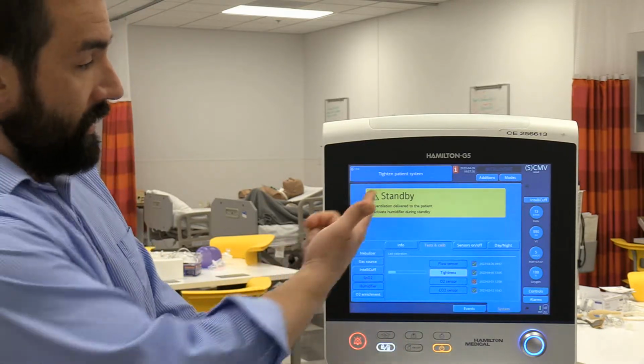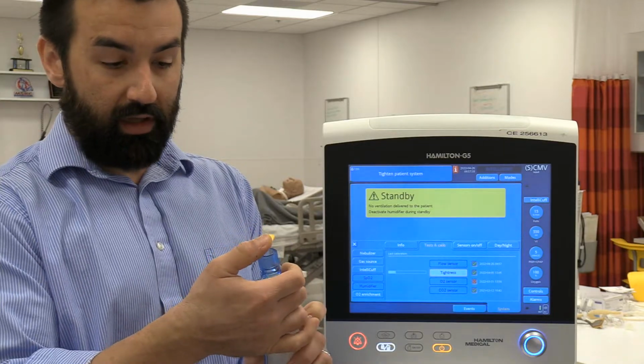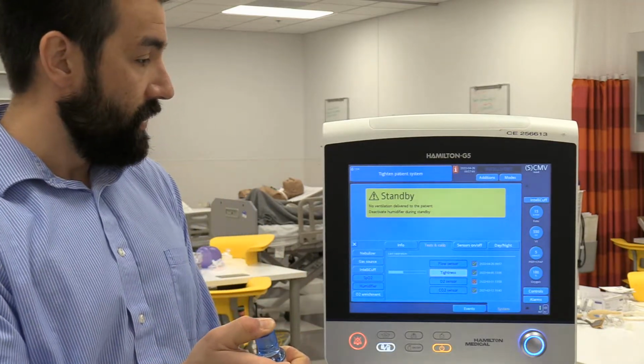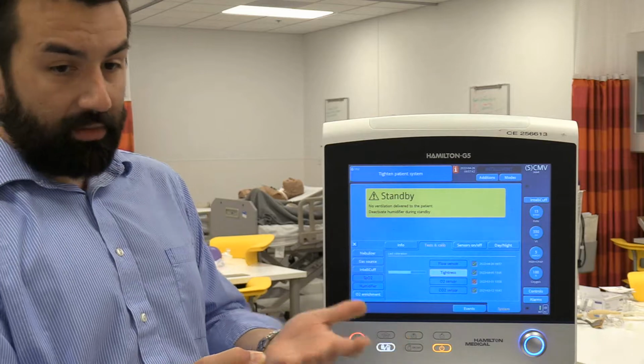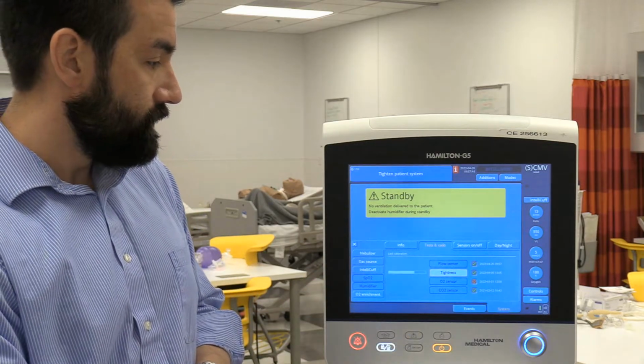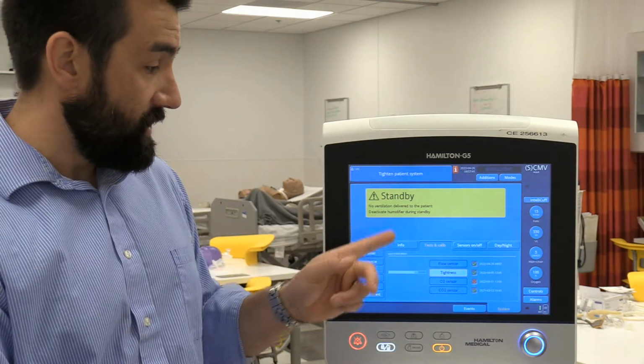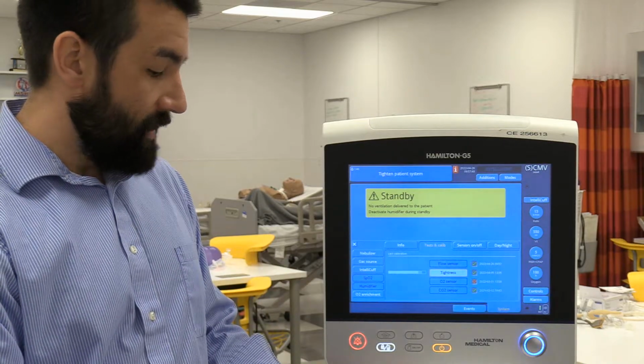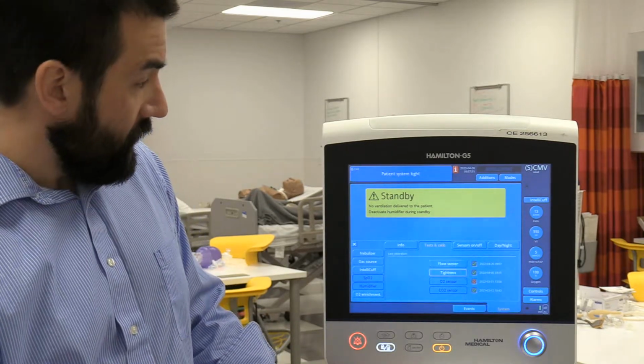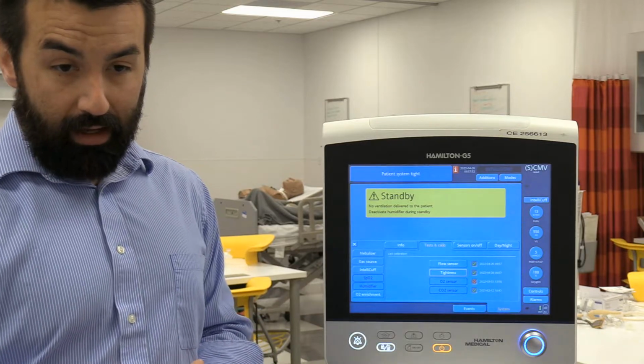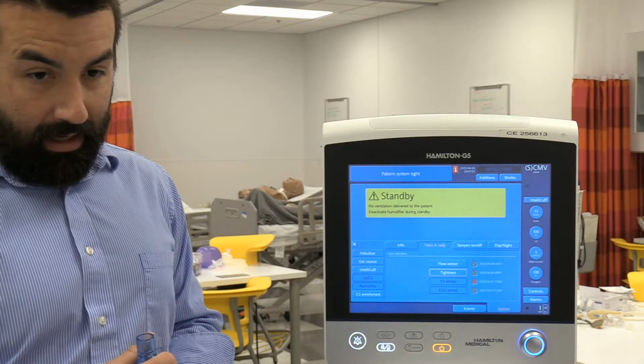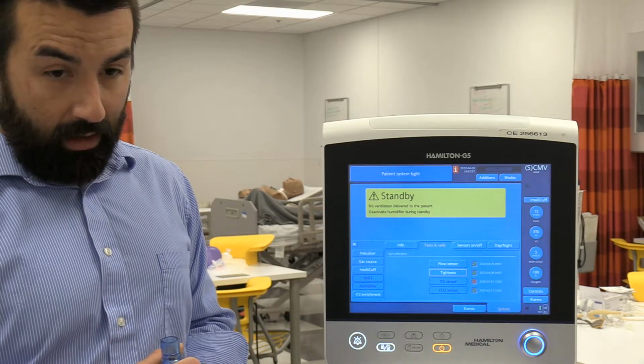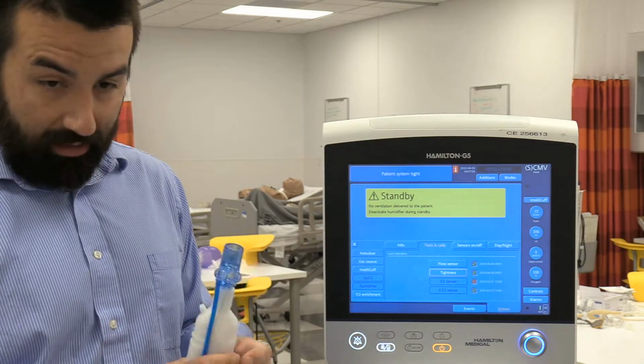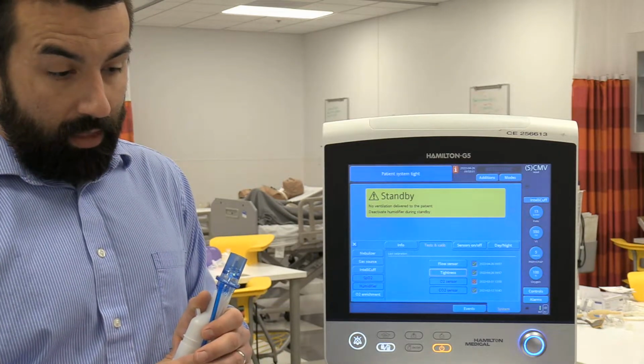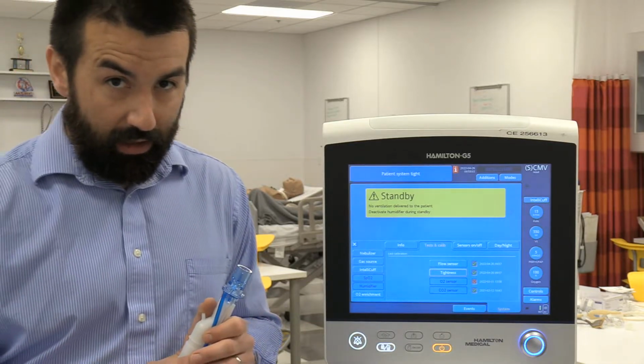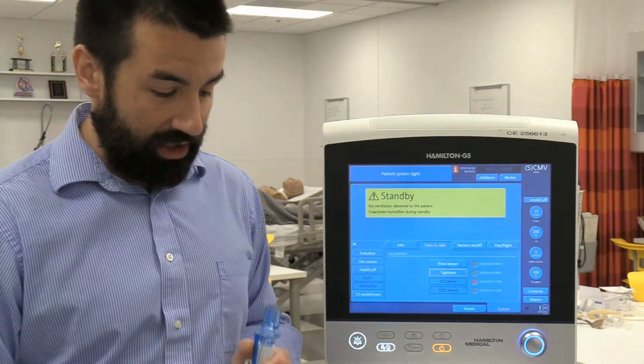So pardon me, it says tighten patient system. I'd use a gloved finger, but the blue cap would be what you wanna do here. You could also, if you're using HME, have that on, make sure everything's all good. It's gonna tell us tighten patient system. All right, I'm tightening it here, making sure everything's all good. It tells me patient system tight. If it's not, and it's getting a leak, all right, make sure you had everything covered up, check the obvious connections and such. In my experience, the thing that is generally bad is on the exhalation diaphragm.